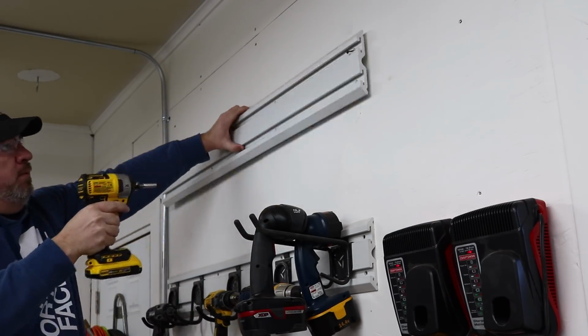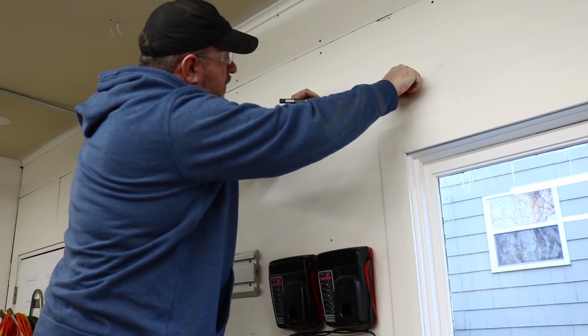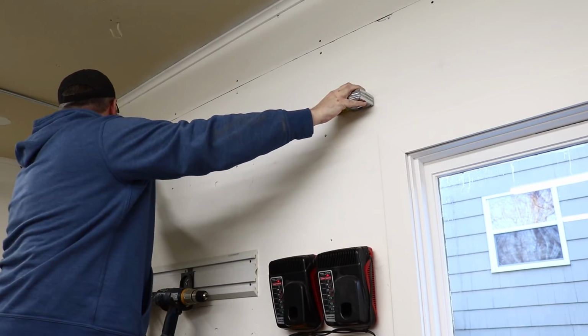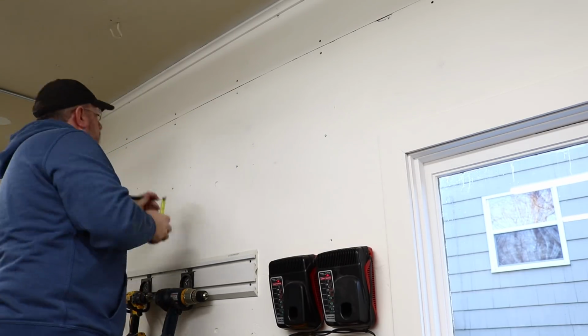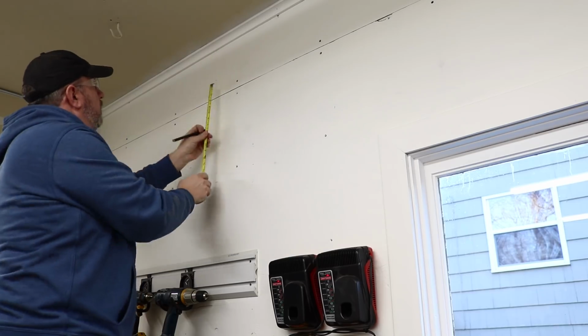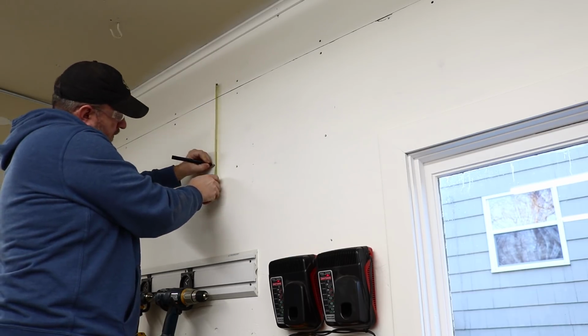To make room for the indoor unit, I had to remove this top row of tool storage. I then moved on to marking out the location of the unit so I could attach the mounting plate. The manual specified the clearances required for the unit and also provided a drawing of the mounting plate in relation to the unit, which made locating the plate very easy.